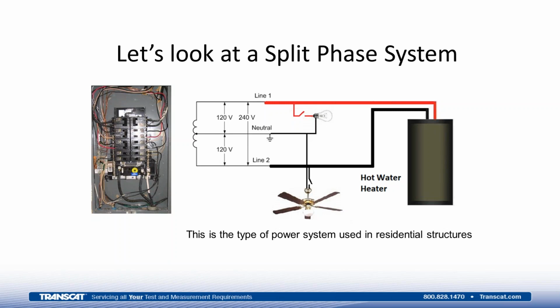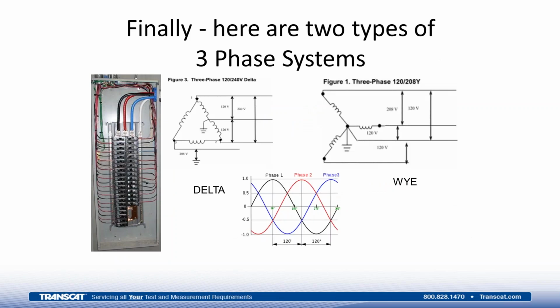In an industrial environment, it would be very common to have a three-phase system, which is demonstrated on this picture. Now, three-phase systems look more complicated, but they're basically add-ons to the two-phase, split-phase type systems that exist. In a three-phase system, there would be three energy sources and possibly a neutral. If you look at the picture of the cabinet on the left, the black, red, and blue are phase conductors that we would identify as L1, L2, L3, or phase 1, phase 2, phase 3, or A, B, and C. And then the white wire is the neutral that would be used in this system.